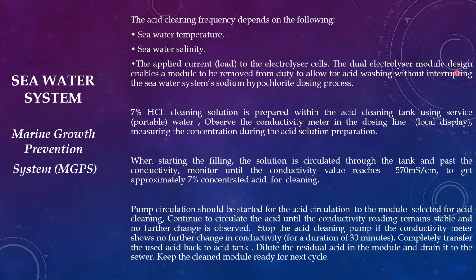The dual electrolyzer module design enables a module to be removed from duty for acid washing without interrupting the seawater system sodium hypochlorite dosing process while the seawater pump is running. So one module will be in service, and the other module, if it is getting hot scale inside, can be taken for acid cleaning. 7% HCl is normally used.